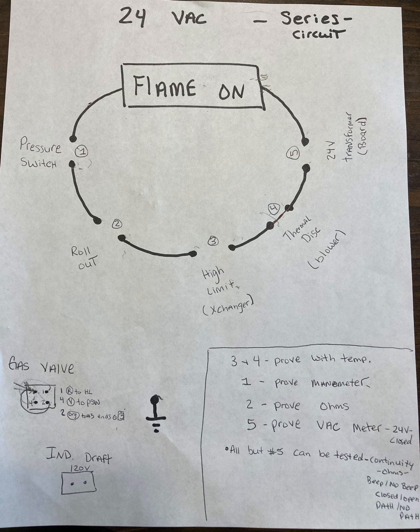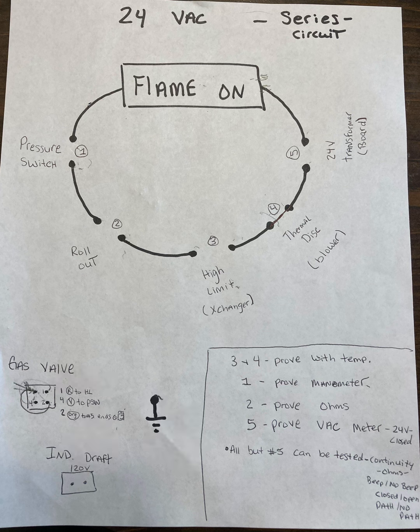I did add this induced draft motor to the board. A lot of times, we need to test it right there, and we can hopscotch the same way. One on the ground, one onto the power leg of that induced draft motor. It's only got 2 wires going to it. Do I have voltage or do I not? And if I have voltage right there at that pin, man, I do have 120 volts there, and that motor's not coming on, then the motor's bad.